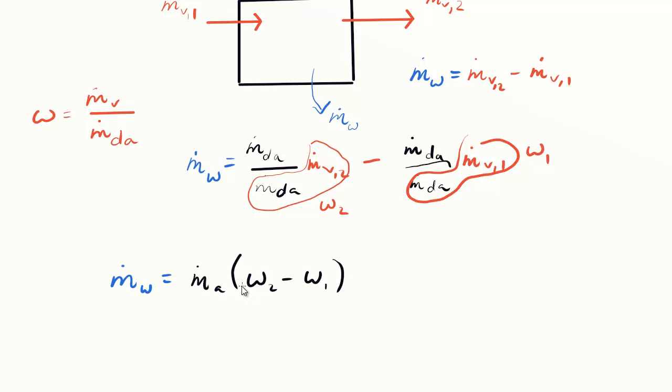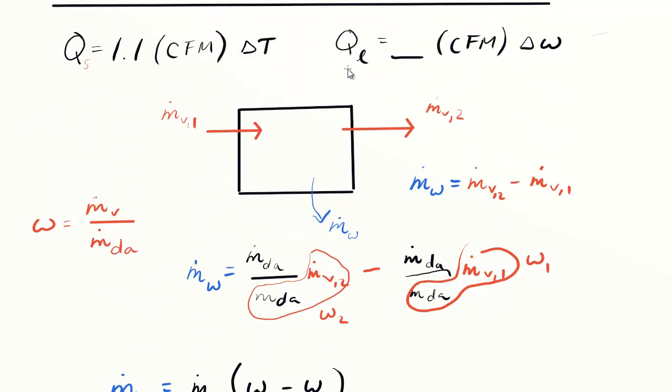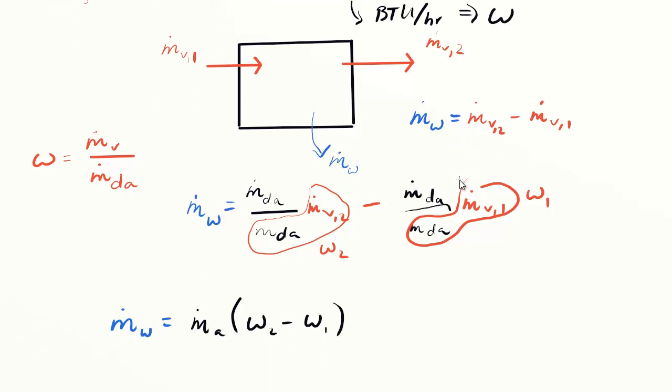Now we want a shorthand formula that gets us a heat load in units of BTU per hour, or in SI, watts. We need a factor that takes this from units of pounds to our heat transfer units. What we need is the latent heat of vaporization or condensation. If we multiply by that, we get BTU per pound mass multiplied by pound mass per hour, which gives us BTU per hour.